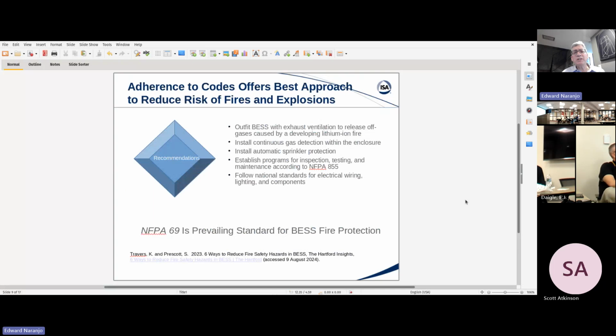Some of the things to be done quite readily is to equip BESS with exhaust ventilation for releasing off gases caused by developing lithium fires. In fact, most containers post 2020 are already equipped with some sort of ventilation system, and I'll go into detail later on as to what their prevalence is. Another one is, as I pointed out, it's necessary to install gas detection or smoke detection within the enclosure. Don't wait until your sprinklers get activated, because there are mechanisms for failure that will not involve radiant heat to be produced. Installing automatic sprinkler protection is also required.